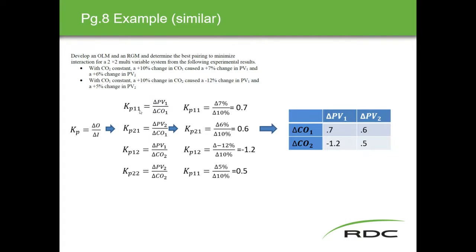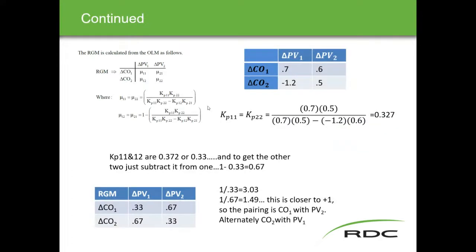In the first loop, controller one to PV1 and PV2, we apply output over input: 6 over 10 gives 0.6, and 7 over 10 gives 0.7. Those go into the grid — position 1,1 is PV1 with controller one, and position 2,1 is 0.6. The second half of the test is generated the same way, and those numbers go into the open loop matrix grid. From there, we plug the numbers into the associated formulas to get the relative gain matrix values.